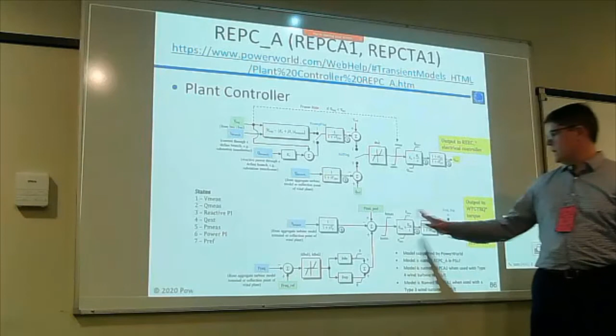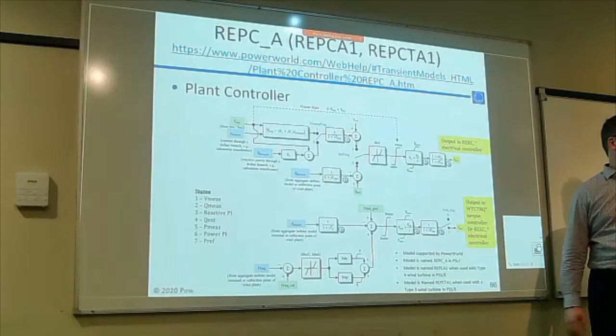If you wanted them to, or if you're thinking about asking them to, essentially you'd come in and set this freq flag to 1, and then you'd come down here and tune this—the droop going down or the droop going up. The droop going up you'd probably set to 0 because the power can't go up. But the droop down, you could set to something, and it would provide governor-type control with the wind turbine. So that's in the model, although no one uses it right now.